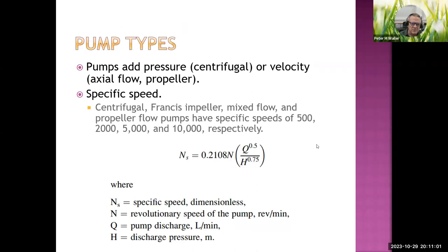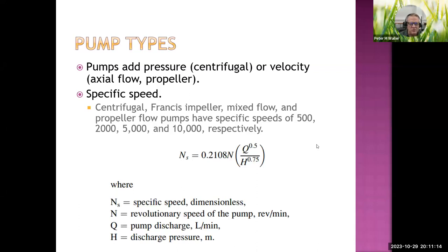There are three or four pump types depending on how you classify them. Centrifugal pumps add high pressure at low flow rate; at the other extreme, propeller or axial flow pumps have high flow rate and low pressure. In between are pumps used in wells that make an intermediate amount of pressure and flow rate, and you might stack them together in a well.